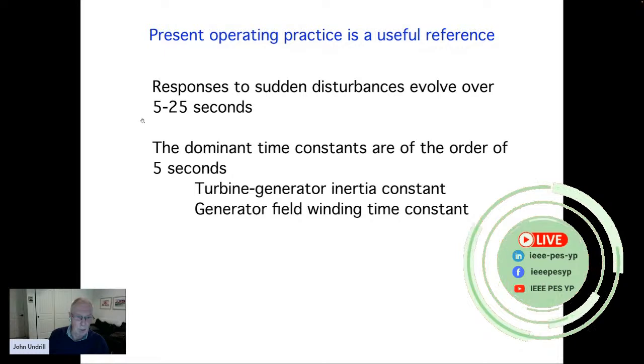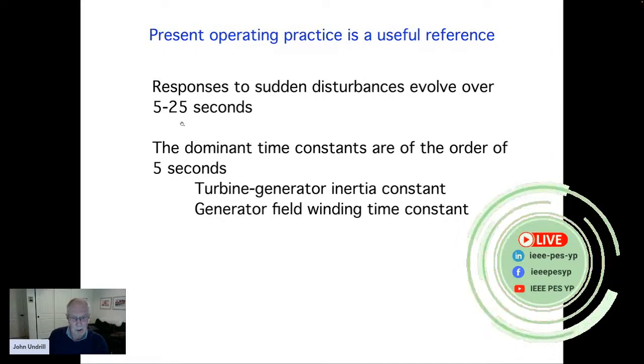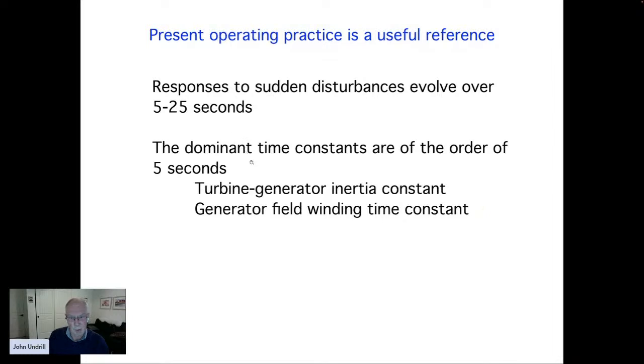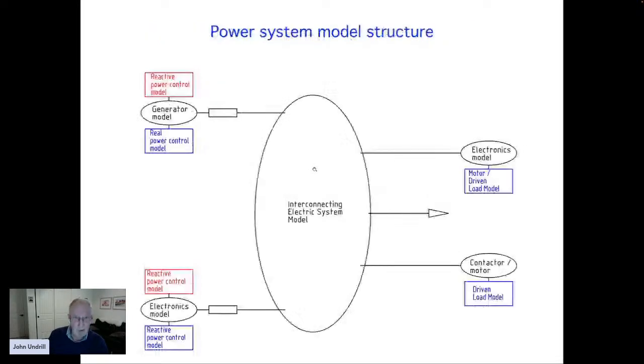We're dealing with a system, when we talk about the rotating synchronous power system that we deal with now, whose behavior is dominated by time constants of the order of 5 seconds. The inertia constant of a turbine generator is somewhere between 2 and 5 or 8 seconds. And the field winding time constant of a synchronous generator, a rotating generator, is somewhere between 4 and 12 seconds, perhaps. So you're not going to be able to make things move instantly. You're not dealing with a rabbit, you're dealing with an elephant. We'll talk about this aspect of a power system.